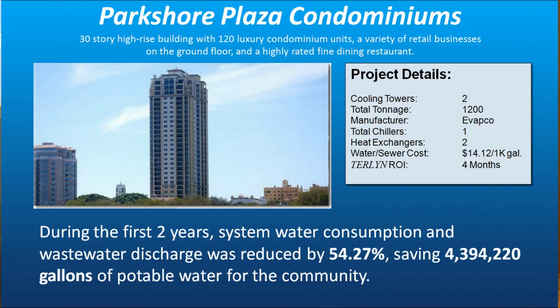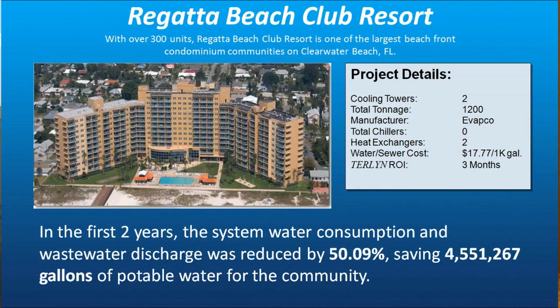Another case study for you, over 300 units. This is another condominium resort, over 300 units. 2 cooling towers, again, 1,200 tons of cooling. Cost of water almost $18 per 1,000 gallons. ROI of 3 months. In the first 2 years, the system water consumption and wastewater discharge reduced by 50%, 4.5 million gallons of potable water saved for the community.